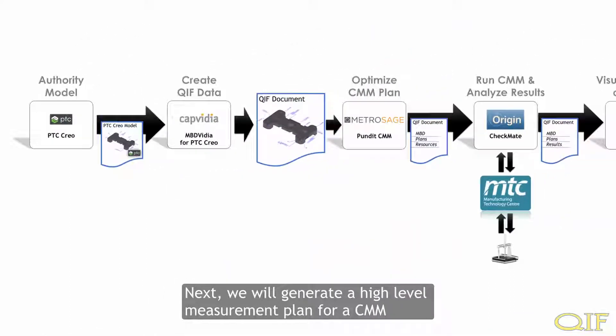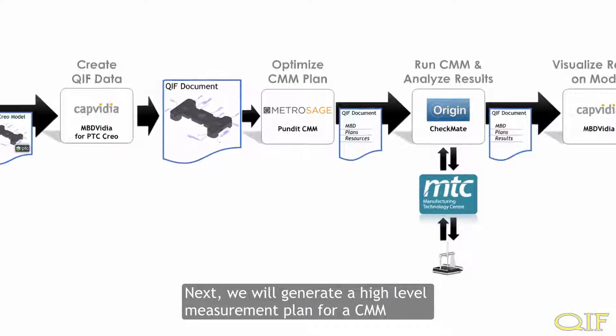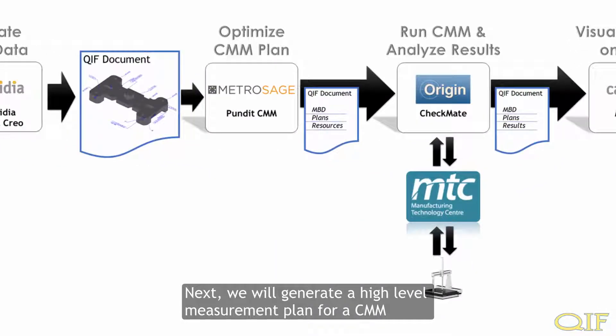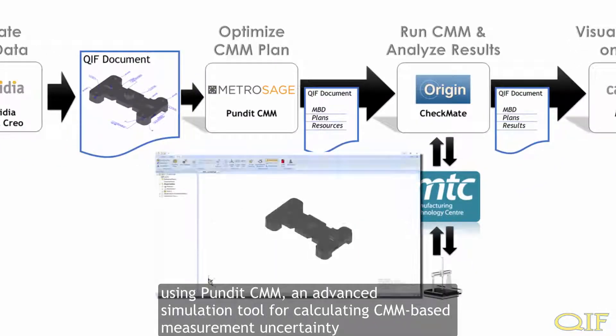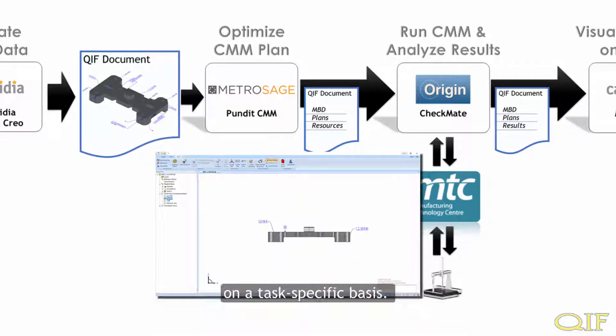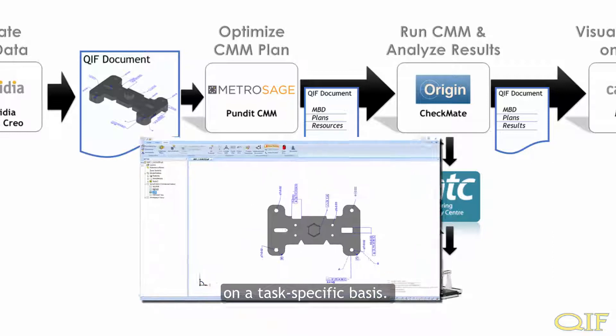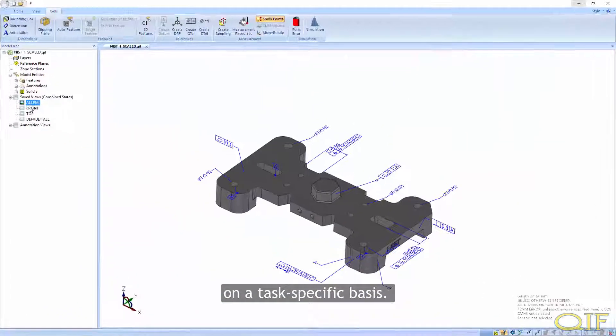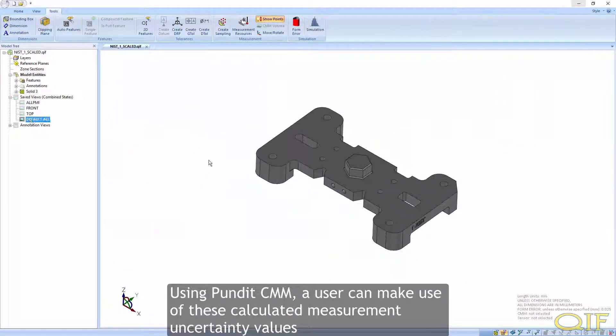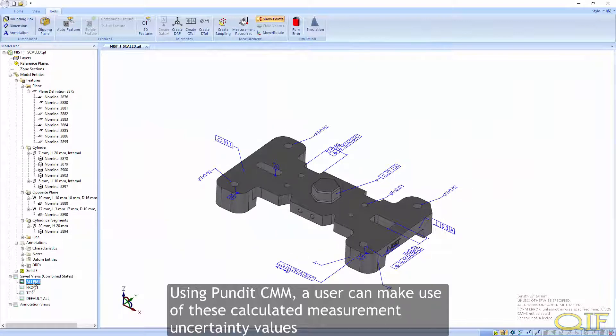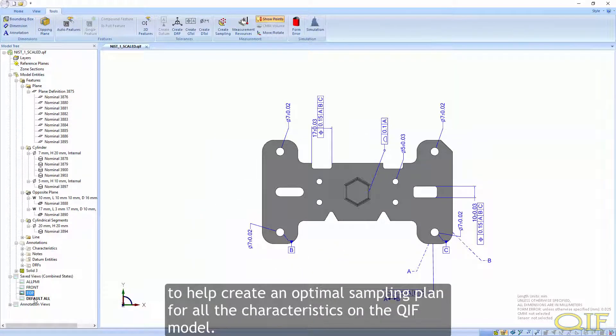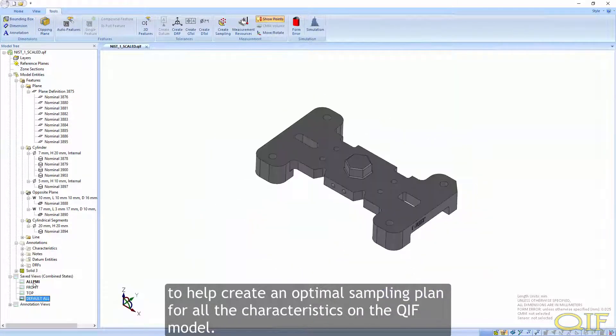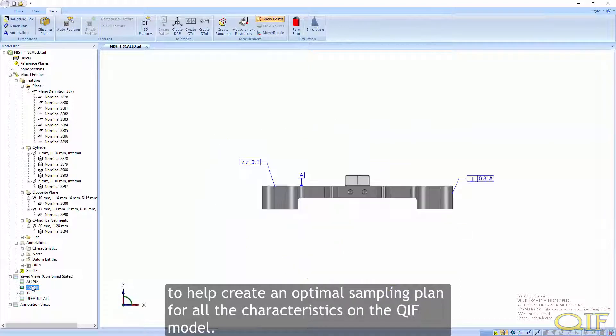Next, we will generate a high-level measurement plan for a CMM using PunditCMM, an advanced simulation tool for calculating CMM-based measurement uncertainty on a task-specific basis. Using PunditCMM, a user can make use of these calculated measurement uncertainty values to help create an optimal sampling plan for all of the characteristics on the QIF model.